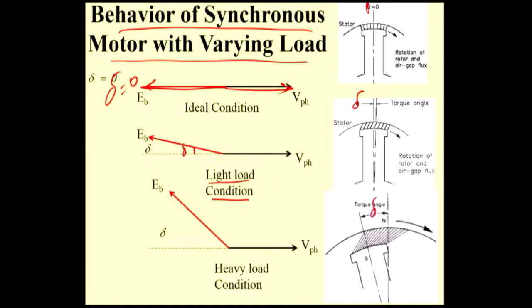You are increasing the load further. What will happen? The rotor tries to come out from synchronism, so delta will be more. If you keep on increasing the load, at one point of time the rotor comes out from synchronism. The synchronous motor will either run at synchronous speed or zero speed. If you increase the load, the delta keeps on increasing, and at one point the rotor comes out from magnetic locking.